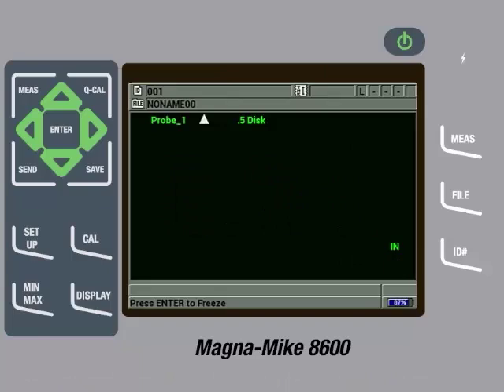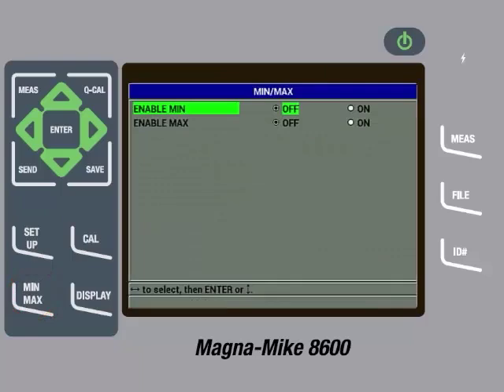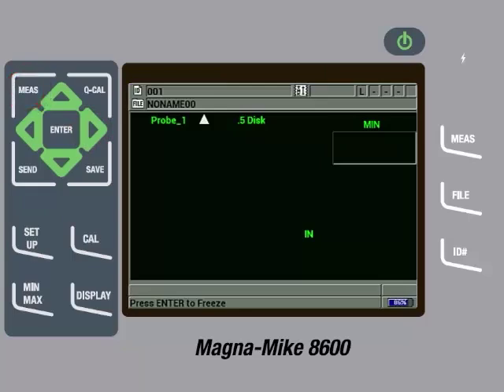on the actual part. The true thickness will be when the target is directly over the center of the probe tip, which also corresponds to the minimum thickness measurement. The gauge will read a thicker measurement when the part is misaligned. For this reason, it is recommended to enable the minimum capture feature. To do this, we will press the minimum, maximum key, and then enable minimum to on by pressing the right arrow. We can then press the measure key to return to the main measurement screen.